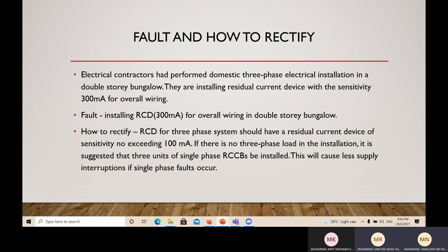The fault is that the contractor is installing an RCD of 300 mA for overall wiring in a double-story bungalow. To rectify it: the RCD for a 3-phase system should have a residual current device with a sensitivity not exceeding 100 mA. If there is no 3-phase load in the installation, it is suggested that 3 units of single-phase RCCB be installed, which will cause less supply interruption on a single-phase fault.